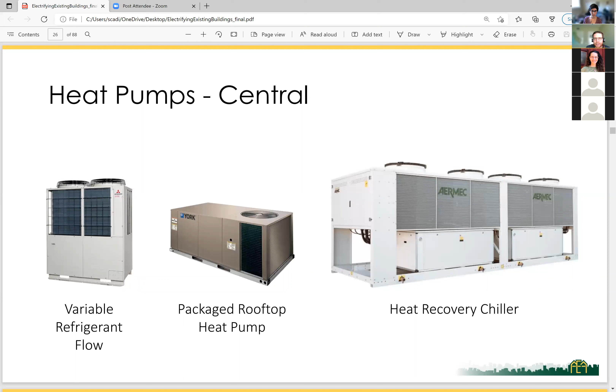One barrier to address is that a lot of older building stock has big central boilers providing hot water or steam for space heating. Electrifying those is still in development—products exist but aren't market ready. So the options are really to move away from those old big central systems and add HVAC at the individual space level. This is way more efficient, but there are construction details and costs that need to be worked out to go from a centralized system to a unitary one. Otherwise, additional products may come online that can replace big gas boilers with a new high efficiency electric heat pump that makes hot water.